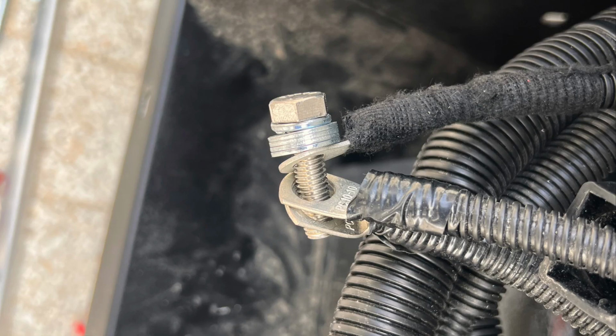The other thing that I discovered was the negative terminal. There are several items which are connected directly to the batteries, which mean that all of these items bypass the shunt. Because there's so many terminals connected to the negative point, the original battery screw wasn't long enough, so the electrician who installed it used a longer screw. But the screw was too long, and what he did was he just put a whole stack of washers there just to be able to get a contact for the negative points. I don't think that that's the right way to do it, and I think that Crusader should be a little bit more fussy about its electrical setups, especially since this is a safety item and we could end up with a lot of problems.